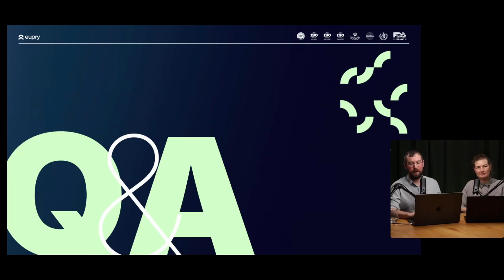We have just a few minutes left, but let's run through some of the great questions. From Melanie here, I'll see the actual parameters, risk-based parameters, and then the parameters of the stability of the product. Exactly, it all depends on the individual products. What we're talking about here is maintaining a controlled state, ensuring that at least your calibration is in order. When you have excursions, there was also the question before about why I would need to have calibration outside my desired operational range. Well, that is because you need to assess, when you have excursions, what the impact of those was.